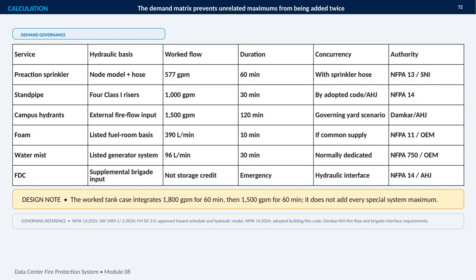This slide establishes how fire protection water demand is governed across different services. The key principle is that each system is calculated from its own hydraulic basis, duration, concurrency rules, and governing authority. For example, the pre-action sprinkler demand is 577 gallons per minute for 60 minutes, while standpipe demand is 1,000 gallons per minute for 30 minutes. Campus hydrants use a separate external fire flow input of 1,500 gallons per minute for 120 minutes, and special systems, such as foam and water mist, follow their listed design basis.